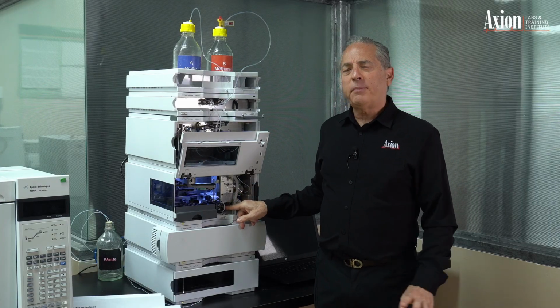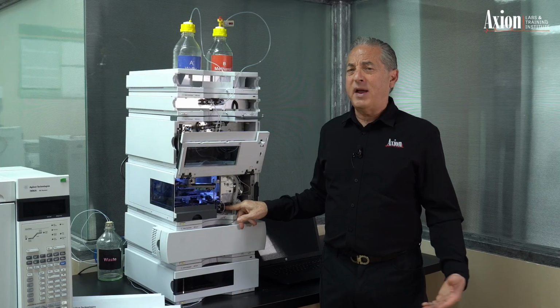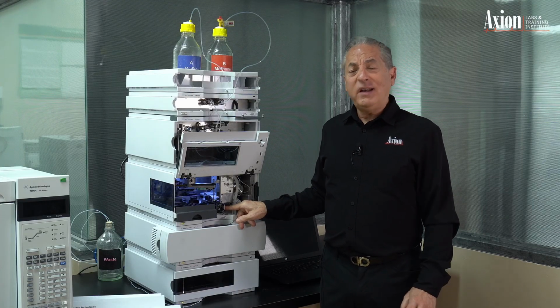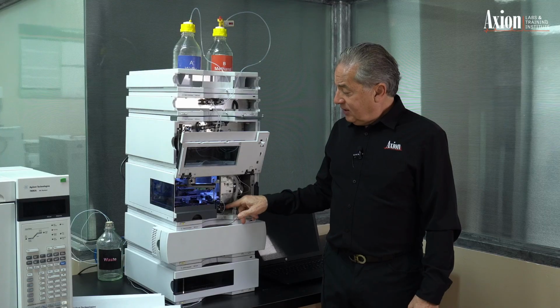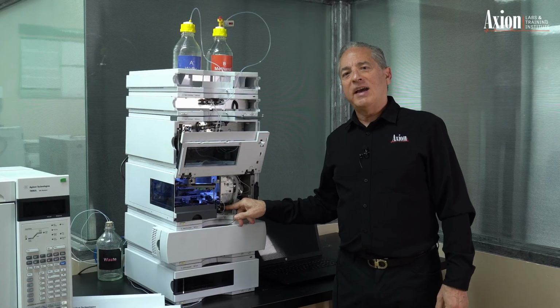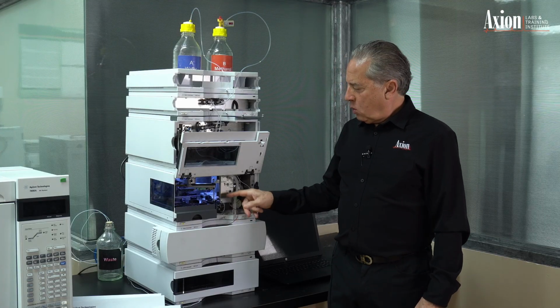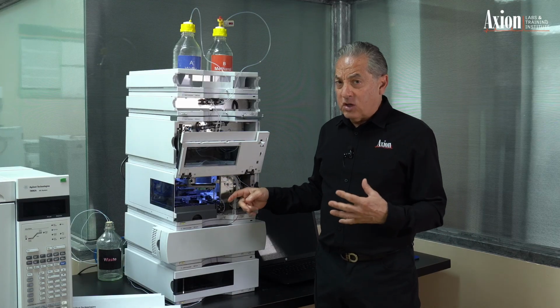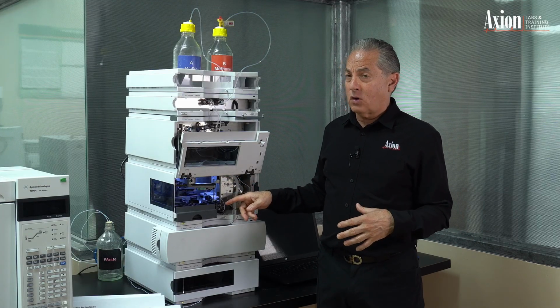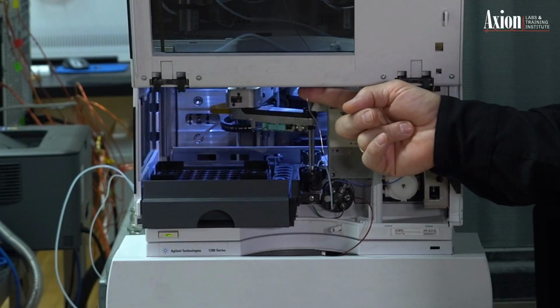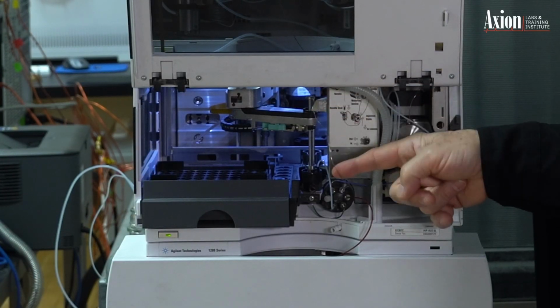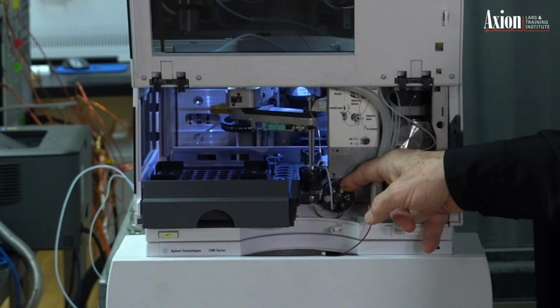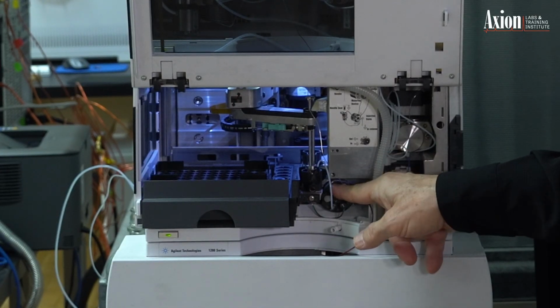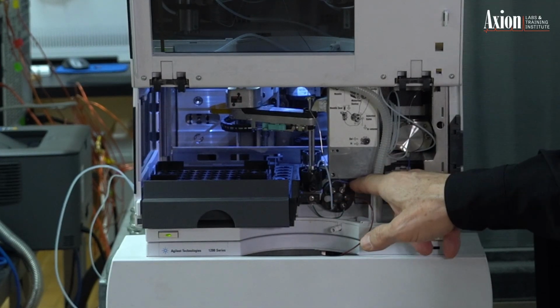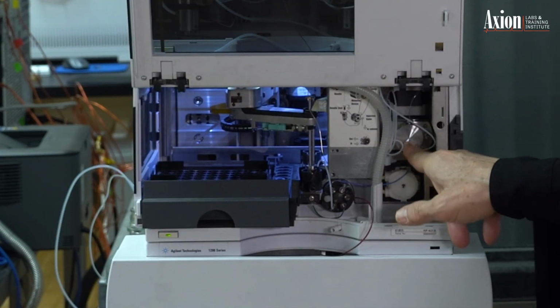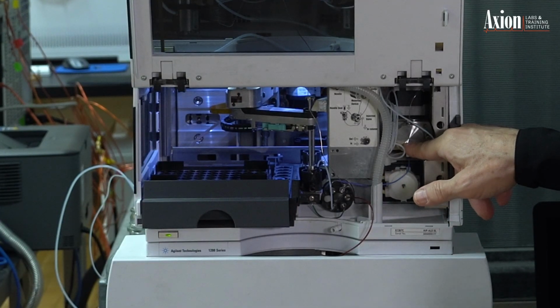So every autosampler in the world has that same injection valve made by Rheodyne. It's a fantastic valve. And what it does is it connects a piece of tubing, one fitting, to the fitting next to it. So there's two modes of the autosampler, load and inject, or also called main pass and bypass. So in the main pass mode, we have high pressure flow coming into the autosampler, and it connects right next door. And when it connects next door, it connects to the left, this blue piece of tubing. This blue piece of tubing enters what's called the metering device. It's going to measure our sample.